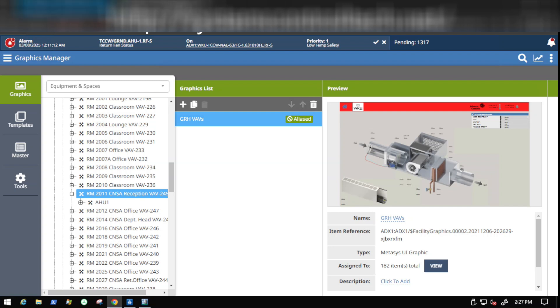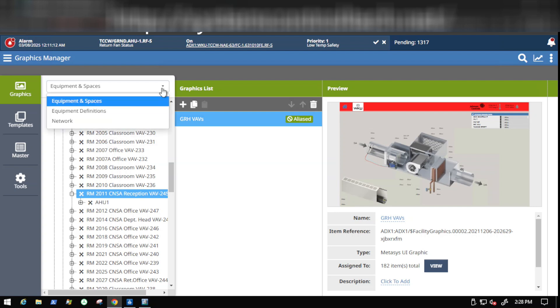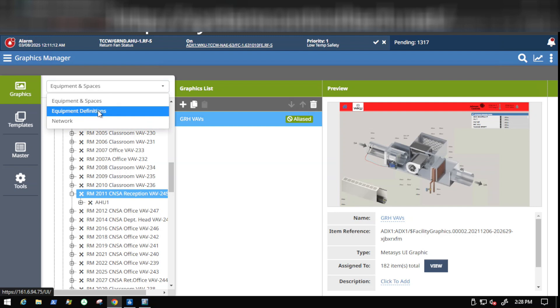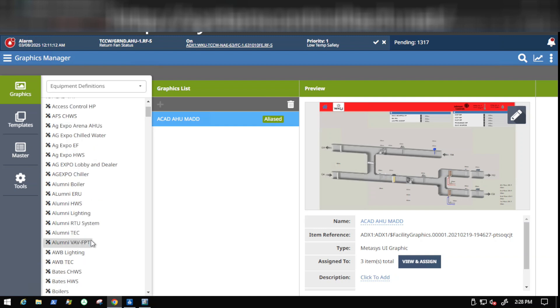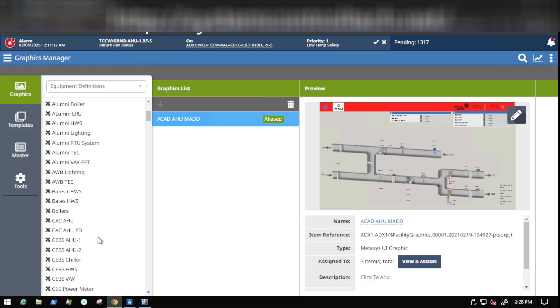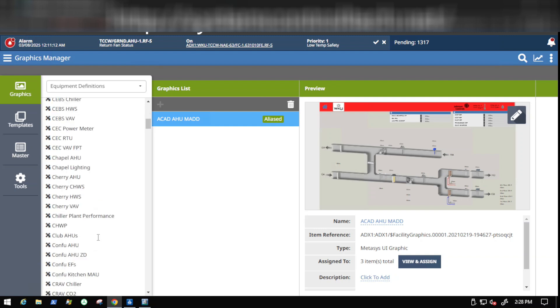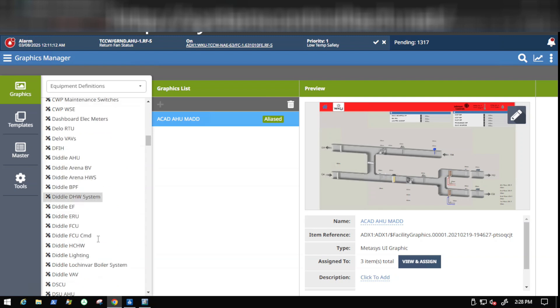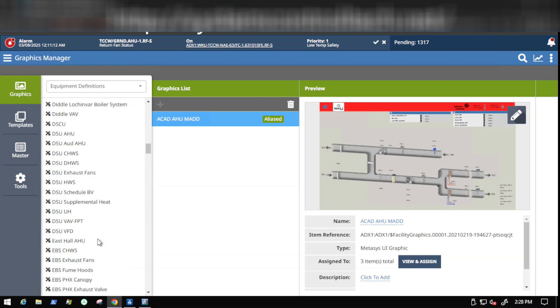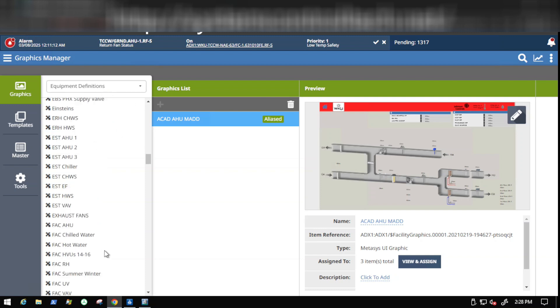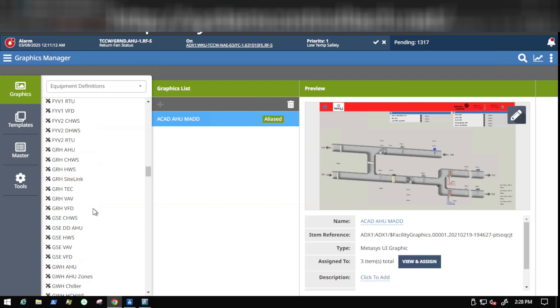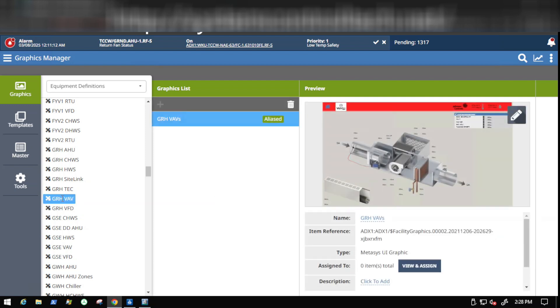You can see that it shows that it is aliased. And what does that mean? It means that the graphic was built not on a particular piece of equipment. It was built on the equipment definition. And this is another point to make as well. If you have a lot of equipment that is similar, such as VAVs, build your equipment graphic on the equipment definition. That way you build it once and it will alias those points for you. I'm going to go to my drop down here, and I'm going to select equipment definitions from the drop down. So when I drill down to the particular equipment definition for those VAVs, it will not let you edit those, it will not even let you enter edit mode if it is showing up aliased, if you do not go into the equipment definitions option. And right here it is, GRH-VAV. This is the equipment definition that all of those VAVs are attached to.